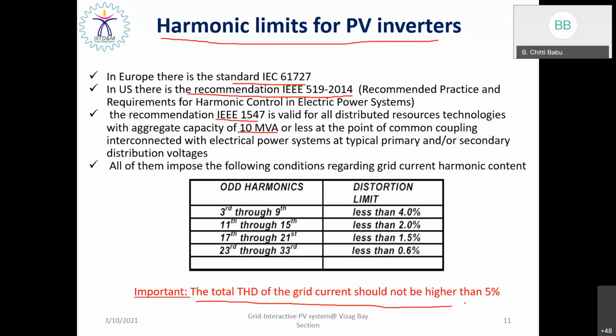Whatever standard you use for grid interconnection, the total harmonic distortion of the grid current should not be higher than 5%. It should be less than 5% according to the harmonic limits imposed by either international standard, IEC or IEEE. But IEEE recommends the limit during steady state, and the IEC is exclusively for the industrial load, including transients.